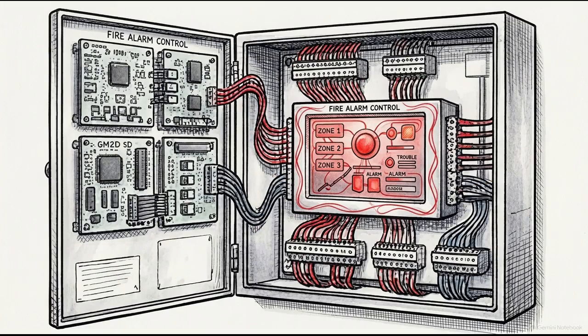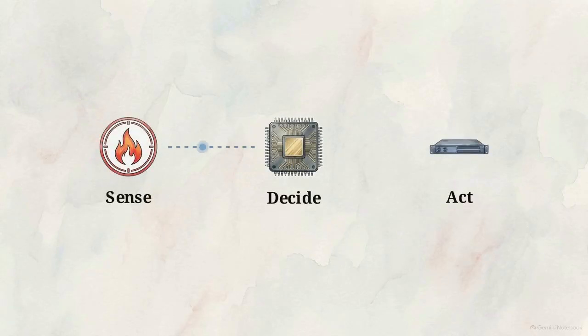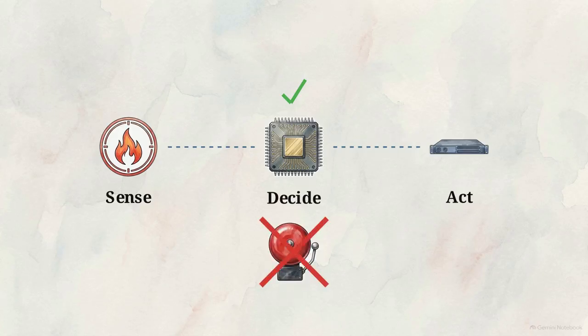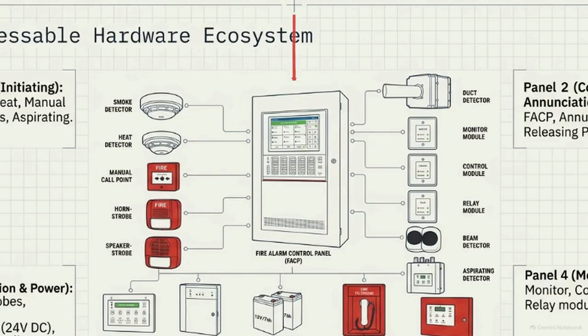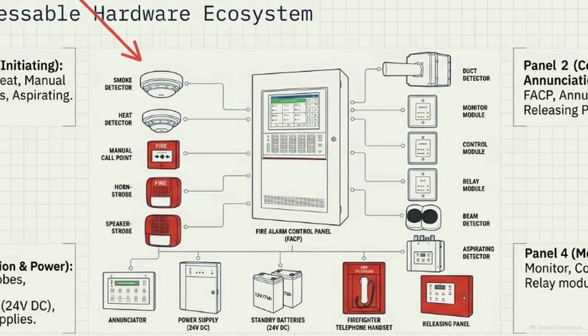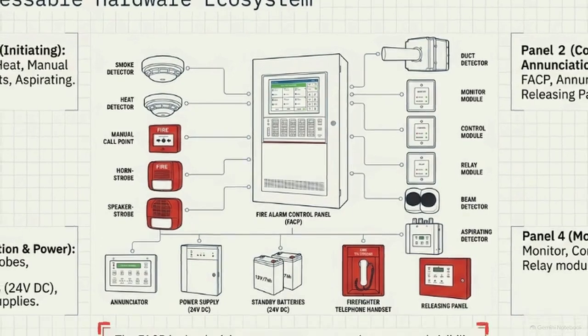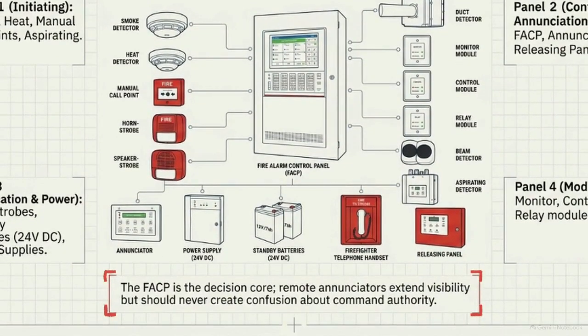To defend against both threats, the fire alarm functions as a high-stakes computational engine, actively sensing conditions and executing decisions based on pre-calculated logic, rather than simply sounding a bell for code compliance. This hardware ecosystem is coordinated by the fire alarm control panel. It acts as the core authority, processing inputs from initiating devices on the left to trigger outputs on the right. Remote annunciators provide awareness, but the FACP alone maintains ultimate command authority.